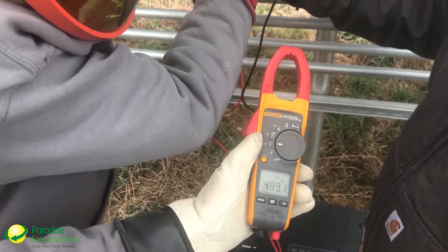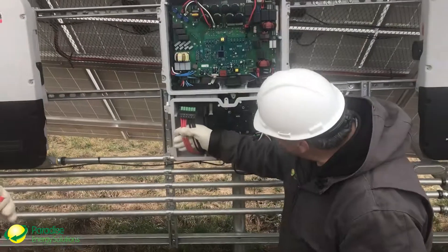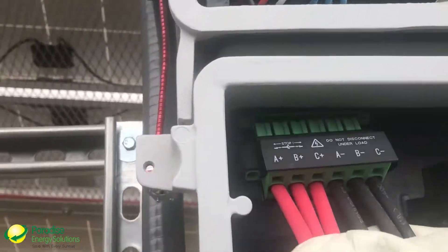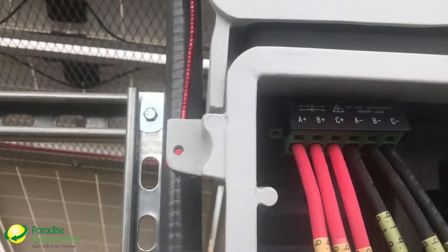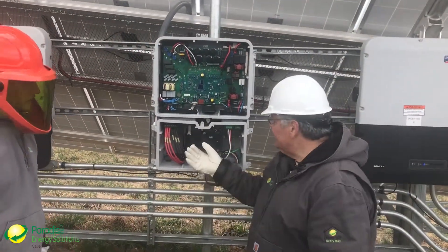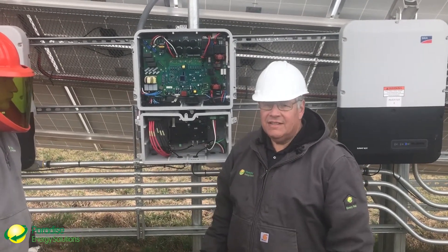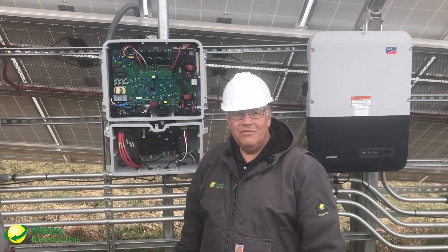Four eighty-nine — four eighty-nine. And Sam, if you can zoom in up here where this goes in, you can see how the connector is going to go right in like that. Once it's landed, Jordan is going to tighten the screws up. That makes the VOC test actually much safer — you still want to have your gloves on, but you're really not removing any DC conductors. Thanks for listening to this week's Tech Tip from Virginia.